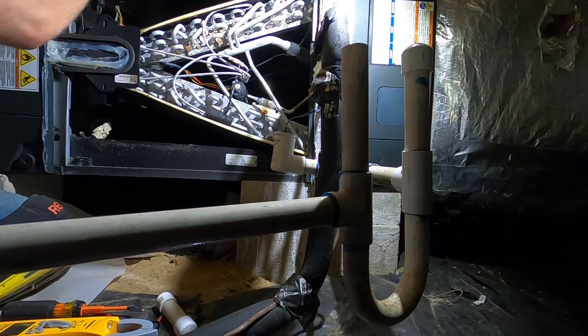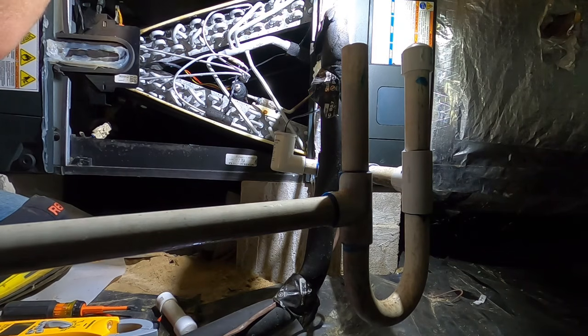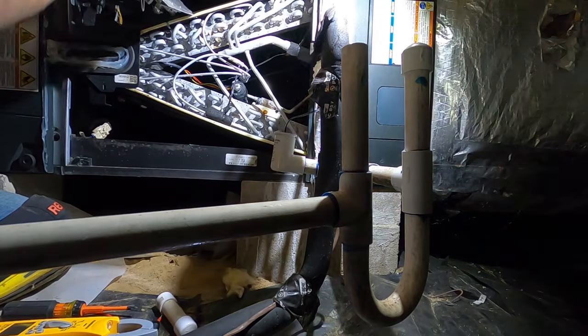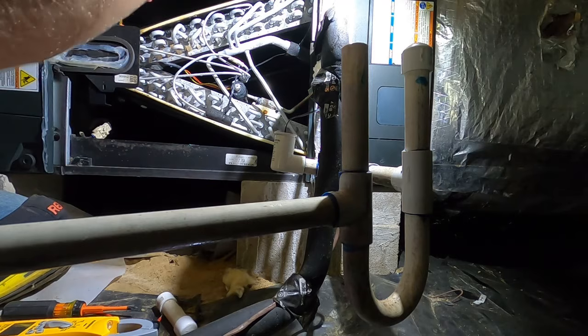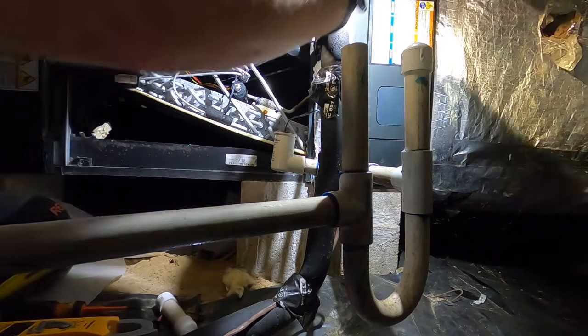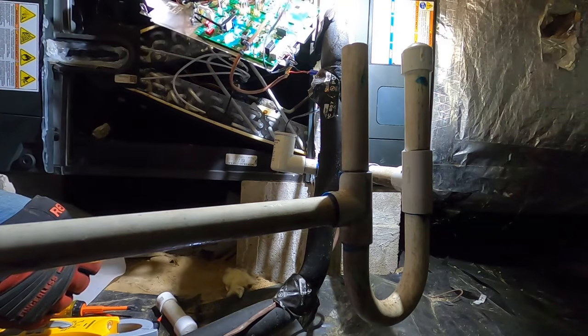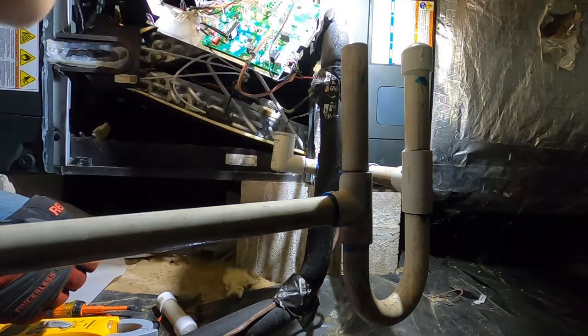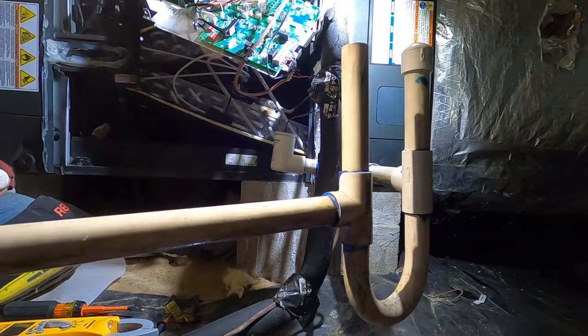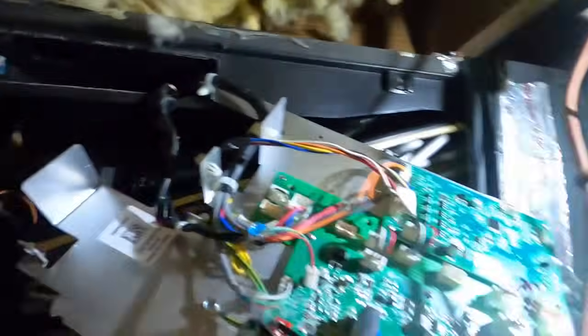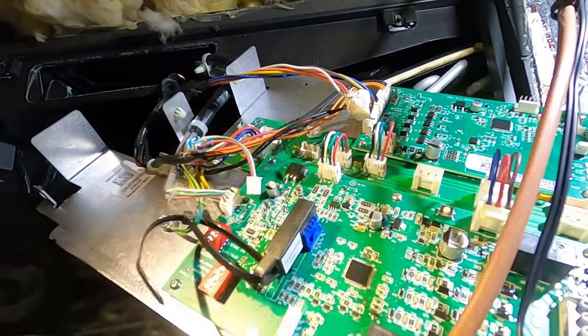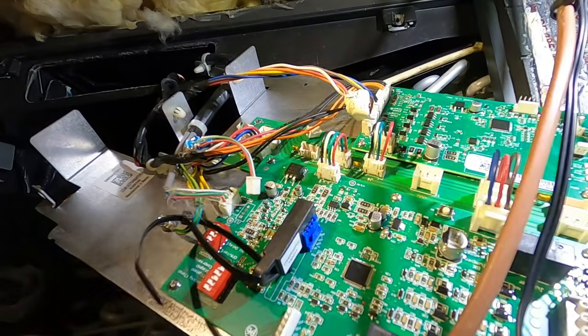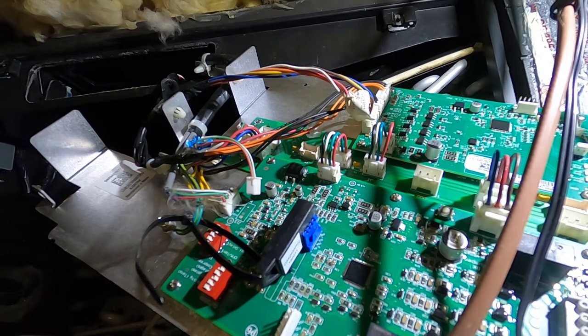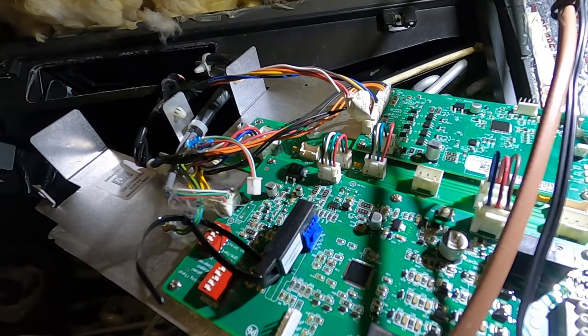And we're going to slide this board out of here and try not to make a mess of my thermostat wiring over there. And then we're going to go over here to these test pins, and I'm going to put the power back on so I can get my DC voltage, but I'm going to get my little needle probe leads going. So we're going to check DC voltage on these terminals, and they should both be reading about the same by now.